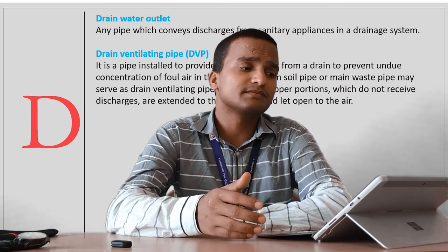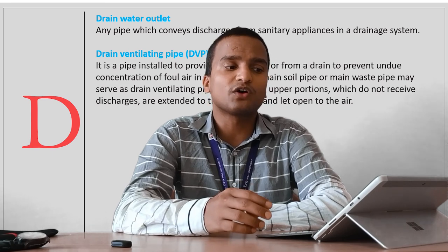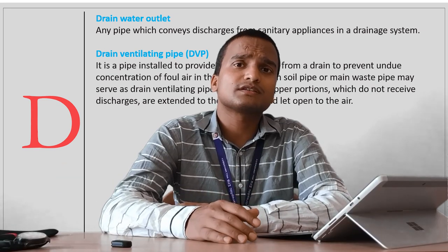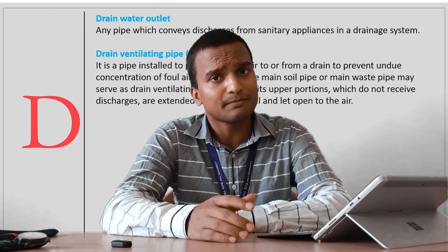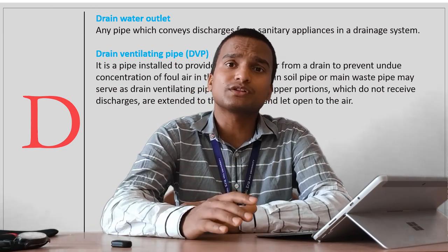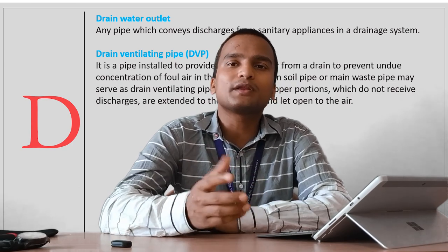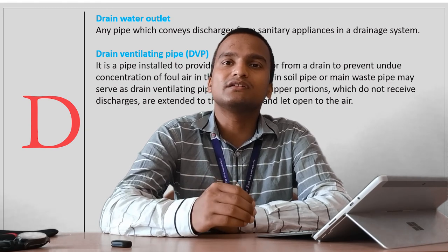And this pipe is provided just outside the home, which is used for ventilation of the air to or from a drain to prevent undue concentration of foul air in the drain, because if that remains there, it can create pressure in the pipe and pipe may burst. In most of the cases, the main waste pipe or main soil pipe may serve as a drain ventilating pipe if in the upper portion they are not receiving any discharges and they are extended to the roof level and left open to the air, and they can very easily vent the air which is being created inside the drain to the outside environment.